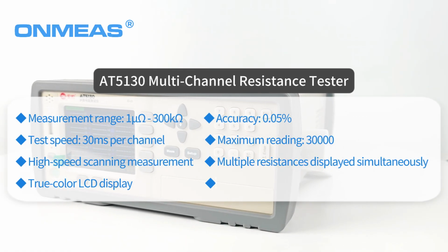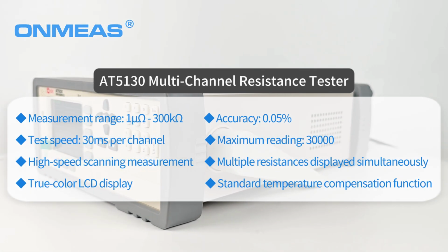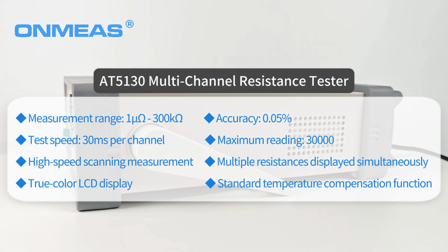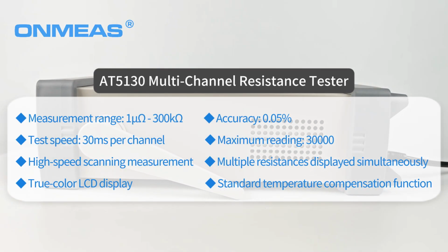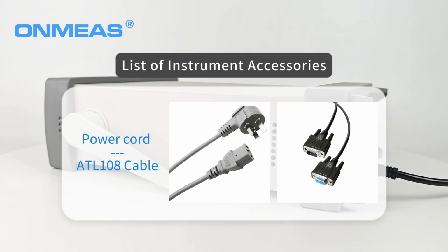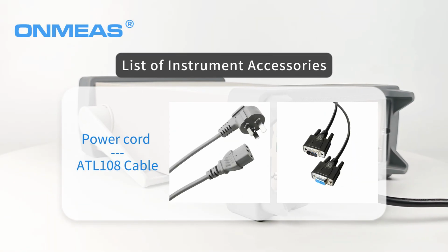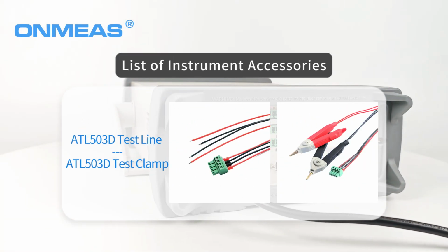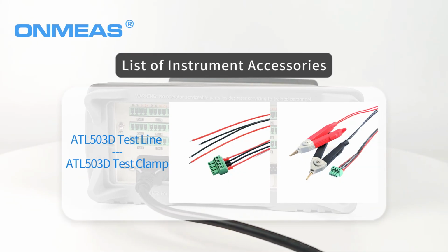The AT5130 multi-channel resistance tester can measure 30 channels simultaneously and display the results on the screen at the same time. Each channel has an accuracy of 0.05% and a measurement range of 1 microohm to 300 kiloohm. The resistance value of each channel is displayed in 5 digits and has 30,000 readings.